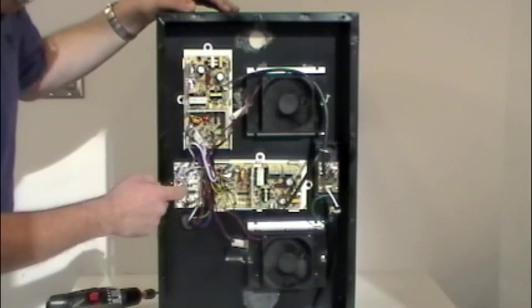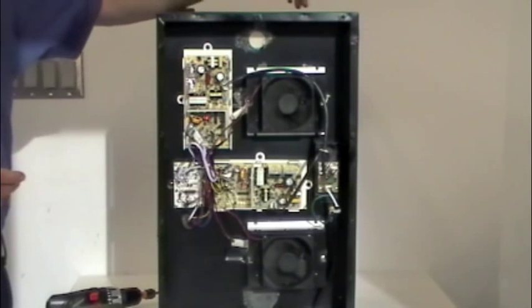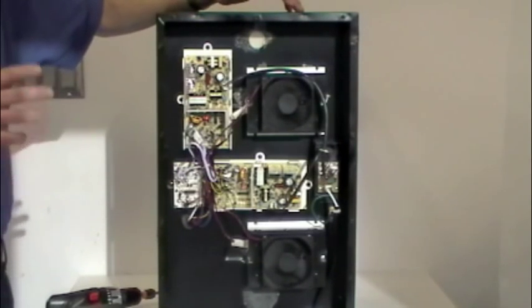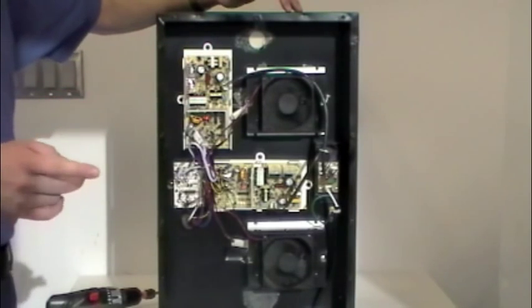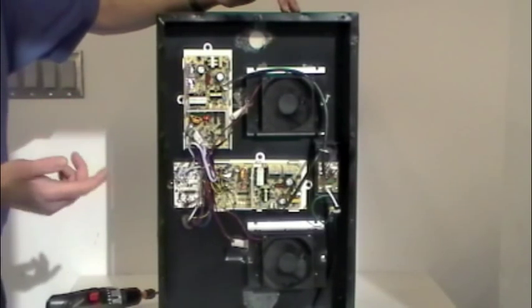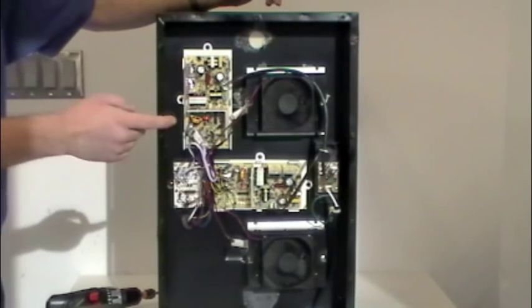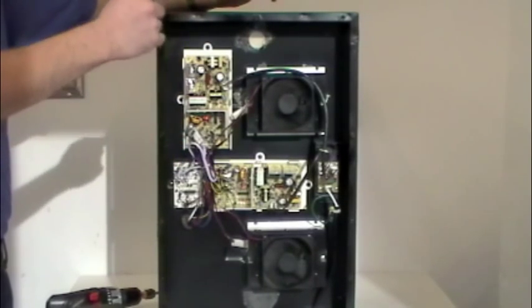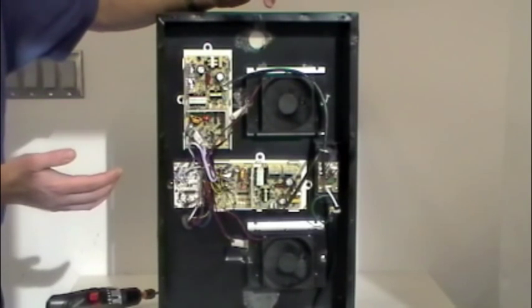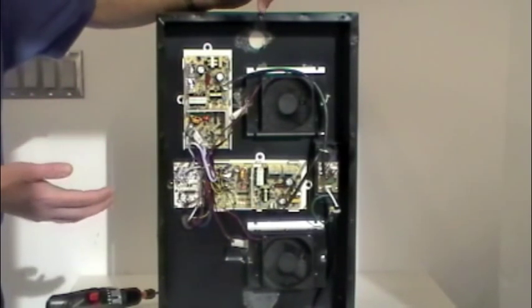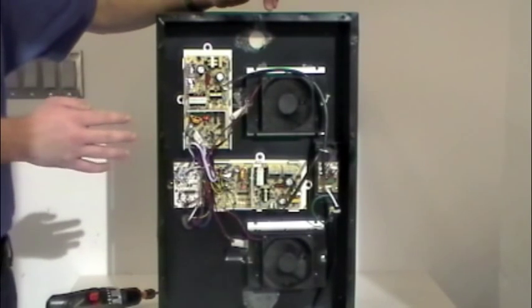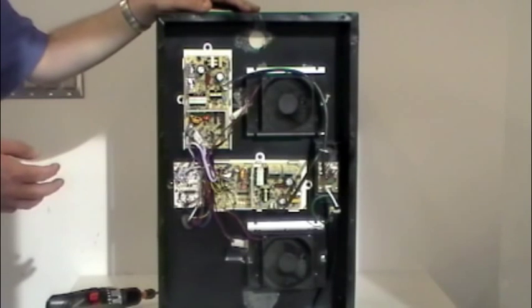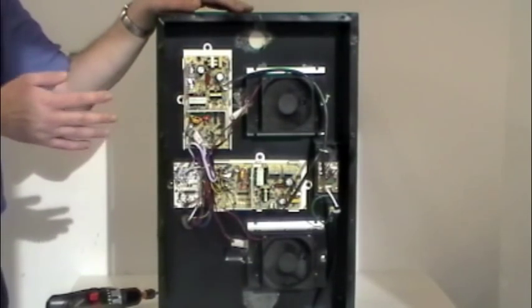The other board over here in the corner, this is our defrost board. Under certain circumstances we can get ice filled up on the inside wall with the cooling node running so cold that any moisture in the air that contacts our heat sink on the other side, or actually our cold sink, it can build ice up on that cold sink. And then what will happen is it gets into the fan, then it tears up the fan, makes a lot of noise. What we've done with this one is an improvement. We have a PTC sensor, positive temperature coefficient, which basically monitors the temperature of that cooling node and the cold side of the sink to make sure I don't get excessively cold. If it does happen to drop that low and it starts to build ice, the unit will disengage the cooling nodes temporarily for a fixed amount of time in order for that to melt off a little bit and then it will restore normal operation. All of these things work together in harmony to make the unit work.